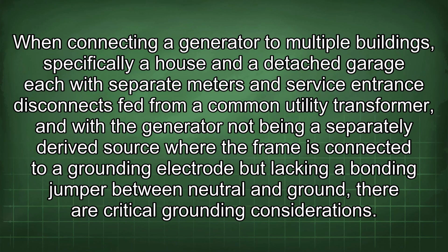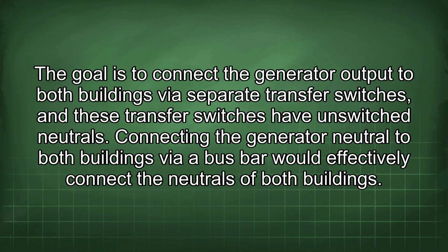When connecting a generator to multiple buildings, specifically a house and a detached garage, each with separate meters and service entrance disconnects fed from a common utility transformer, and with the generator not being a separately derived source where the frame is connected to a grounding electrode but lacking a bonding jumper between neutral and ground, there are critical grounding considerations. The goal is to connect the generator output to both buildings via separate transfer switches, and these transfer switches have unswitched neutrals.